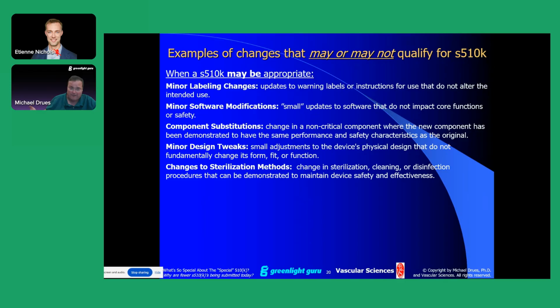Minor software modifications. And again, what does a minor or small update mean? Well, if it doesn't impact the core functions or the safety of the device, then you can probably get away with, and I don't like to use the phrase "get away" because it implies something nefarious is going on, but that's not my intent. I'm simply saying that as long as you can prove that it doesn't impact the core functions of the device or the safety, then you can probably use a special 510K. If you can't, you'd probably need to use a traditional 510K.